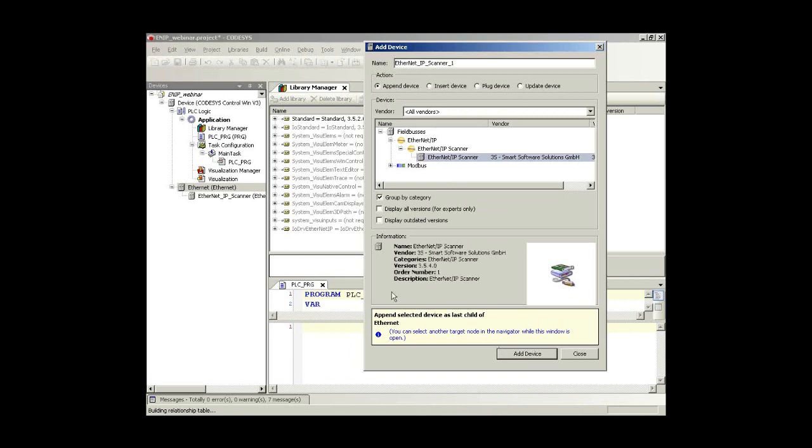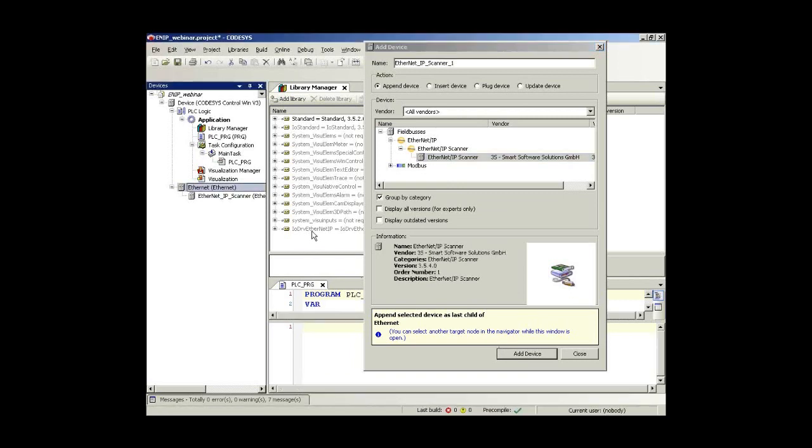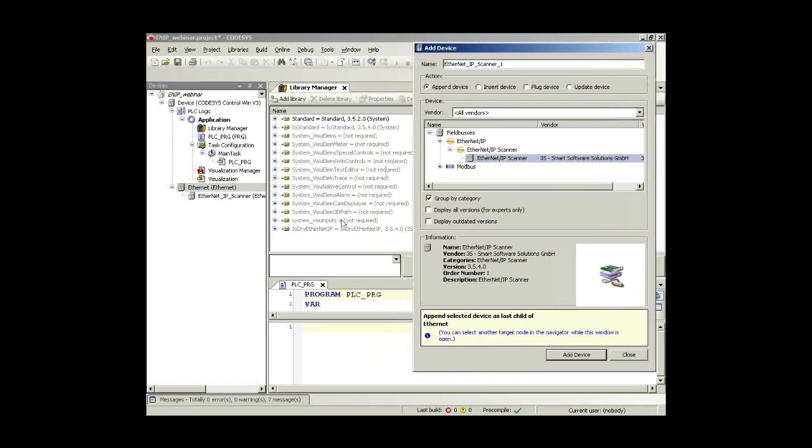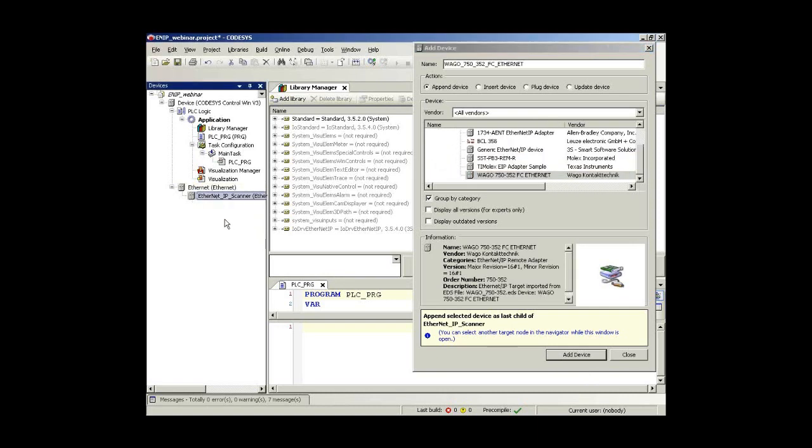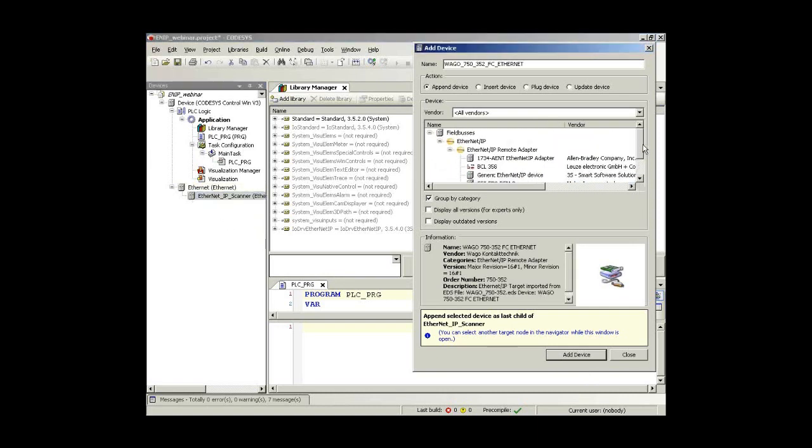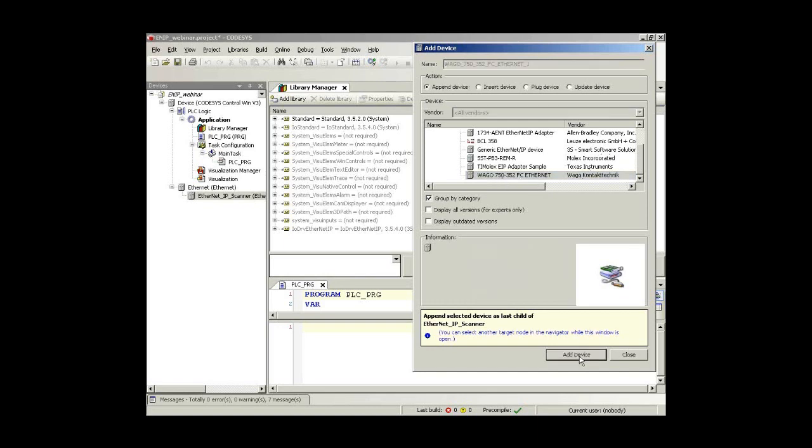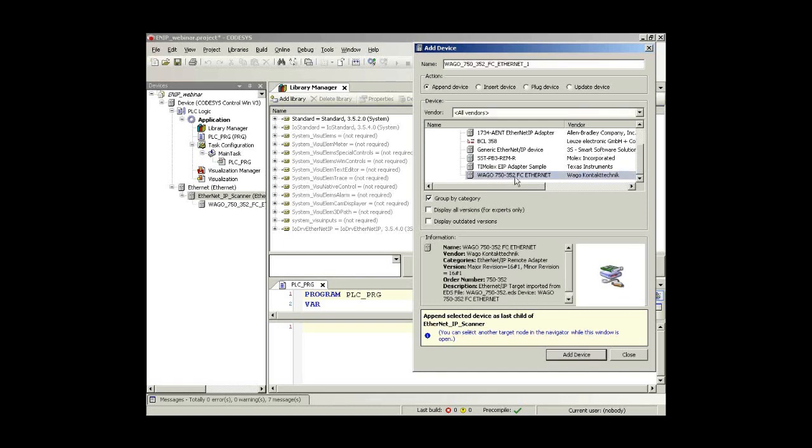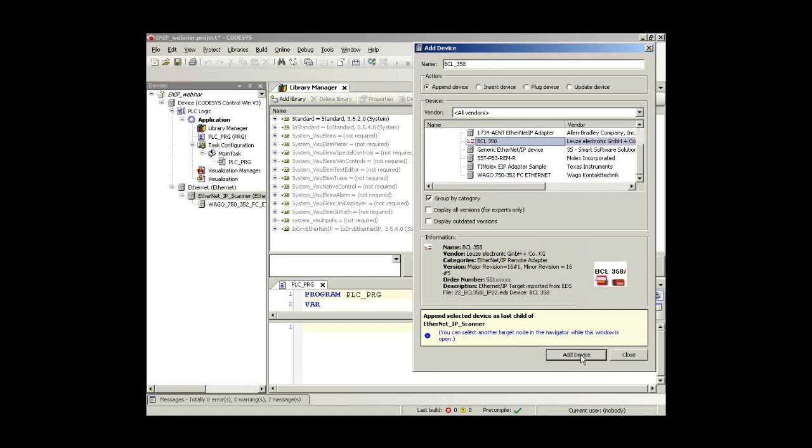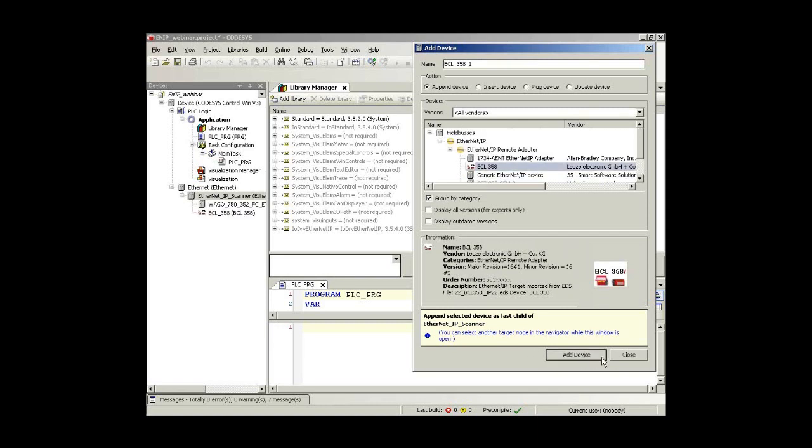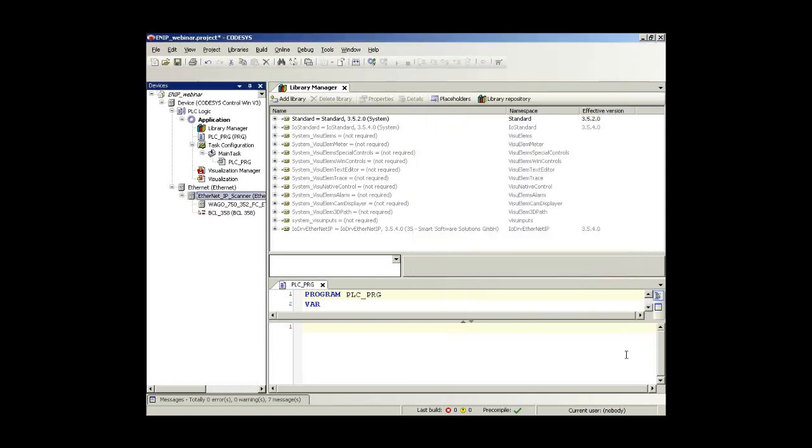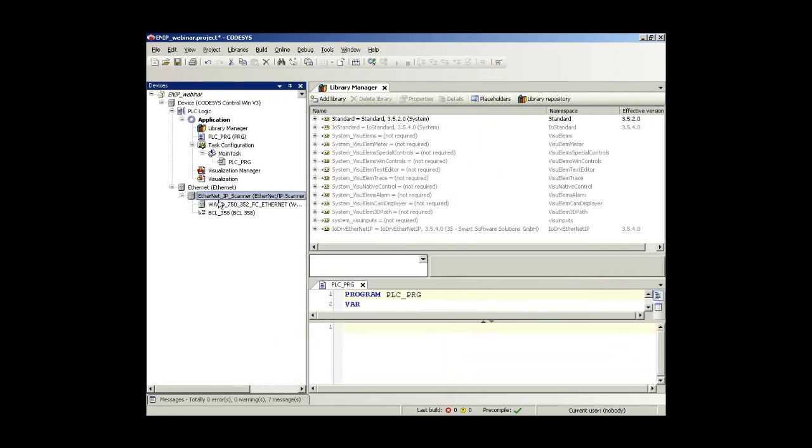As soon as I click on it, I can now choose which fieldbus I want to establish on that Ethernet port. And there I choose now my software EtherNet/IP scanner. Now you see down here that there was a new library automatically included. It's the IO driver EtherNet/IP, which means now the protocol stack was immediately included by including the scanner here in my device tree.